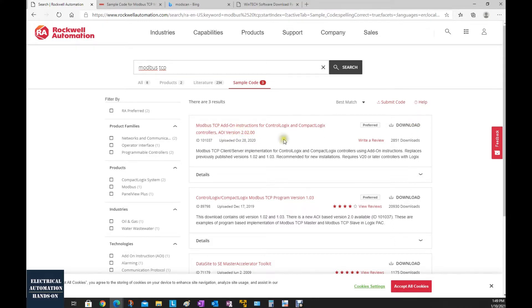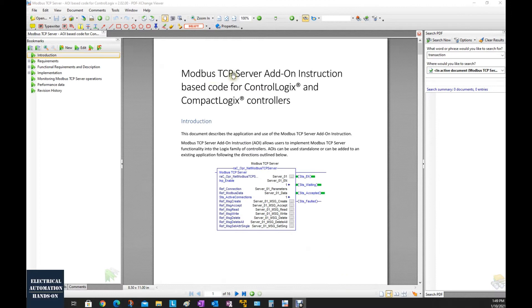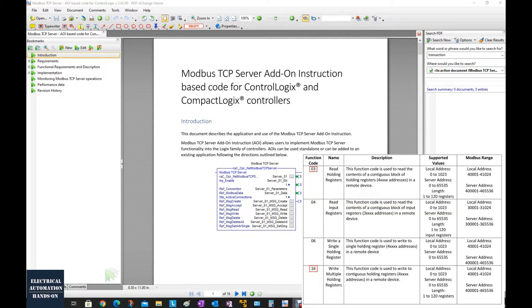Within this AOI, it includes the Modbus TCP client and the Modbus TCP server function. The Modbus TCP server means that once we implement this function, the server will run as a slave, preparing data. From the client side, the client will send a function code — for example, 03, which reads data from the server to the client. If the function code is 16, the client side sends data to the server. So the Modbus TCP server is the passive side — basically we also call it the slave side.